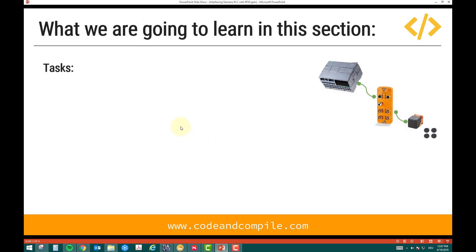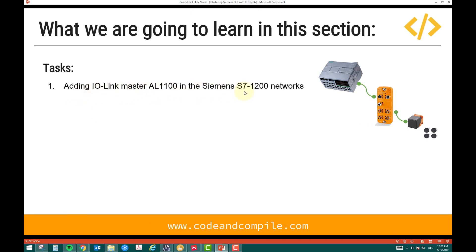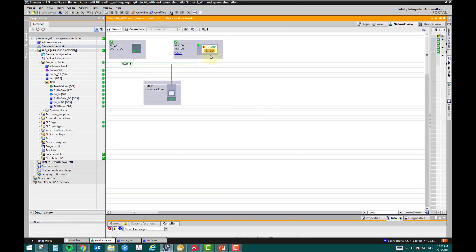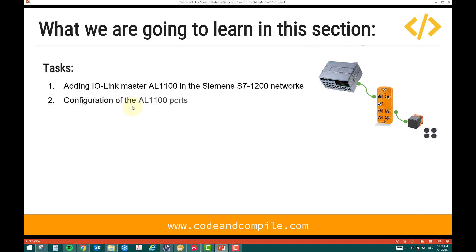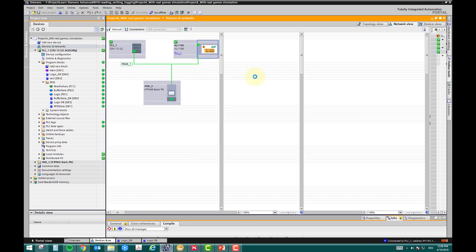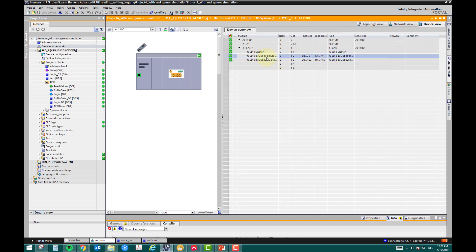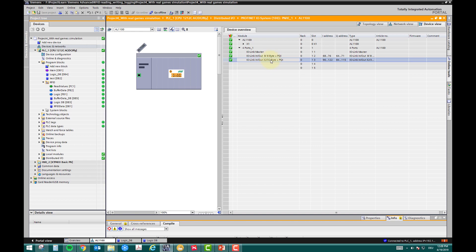What we are going to learn in this section — we have some tasks defined that we will do one by one. The first task is adding the IO-Link master to the Siemens S7-1200 network — I will show you how this block was added, how to configure it. The second task is configuration of the AL1100 ports. Inside the master we have ports — port one, port two — and I will show how to define these ports, for example assigning one port for RFID use.